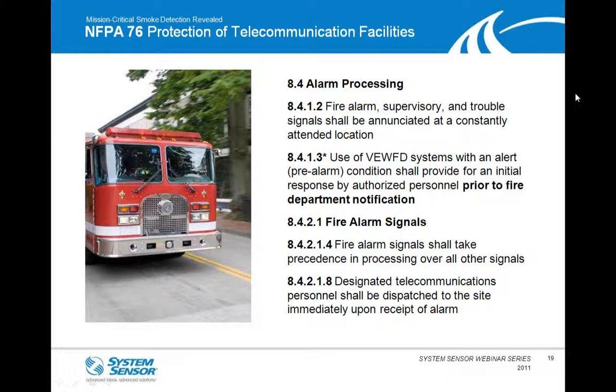And again, it doesn't necessarily have to be aspiration, but more commonly than not, it is. So need to have an alert level that provides a pre-alarm condition. And this needs to be initiated with local, authorized personnel before the fire department's notified. So it's that pre-alarm that they're using to actively manage their system. In addition, fire alarm signals, like in many other applications, need to take precedence over all preceding alarm signals or any other signals. I recognize that with emergency communication systems and mass notification systems, that's slowly migrating, but that has not reached back into NFPA 75 and 76 yet at this time. So the fire alarm signals still take precedence. And designated telecommunication personnel need to be dispatched to the site immediately upon receipt of an alarm. Again, both in that pre-alarm and alarm state.